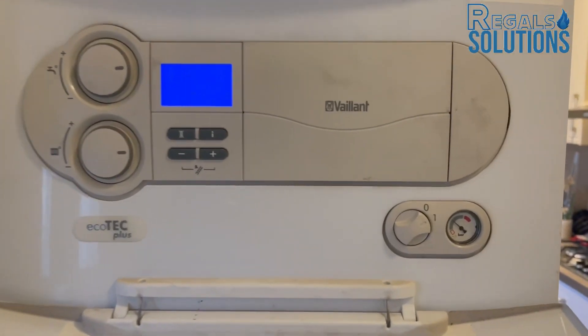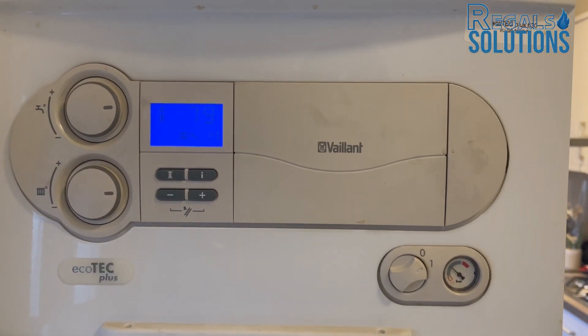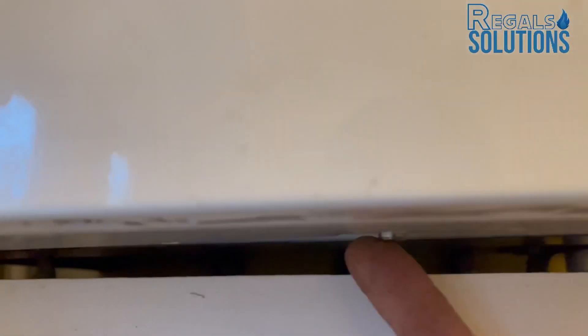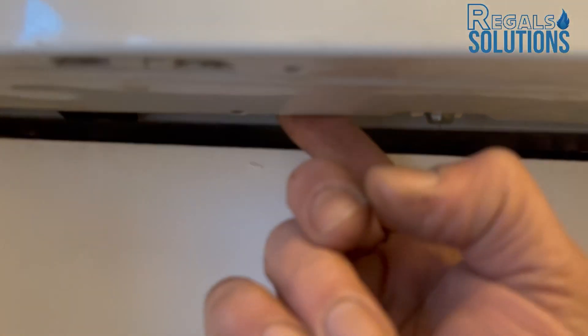Running for 10 minutes — expansion vessel is stable, so I'm happy. Always make sure the screw is in before you tighten it, and make sure these clips are sitting correctly.